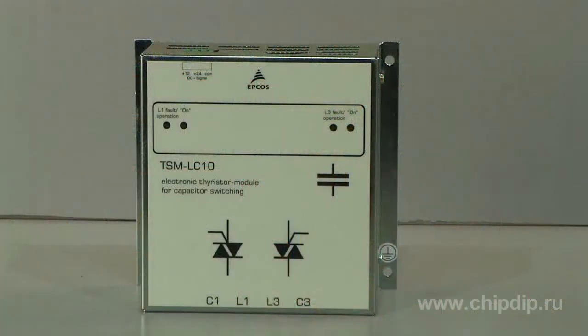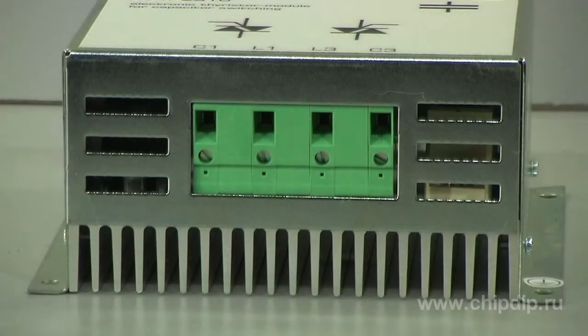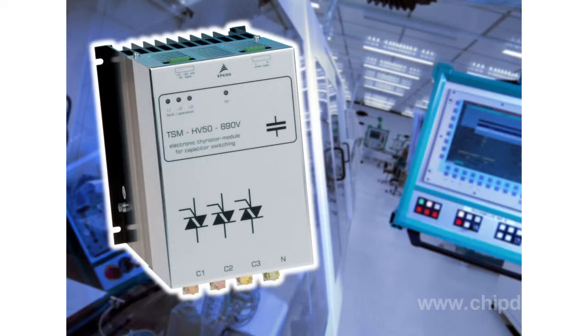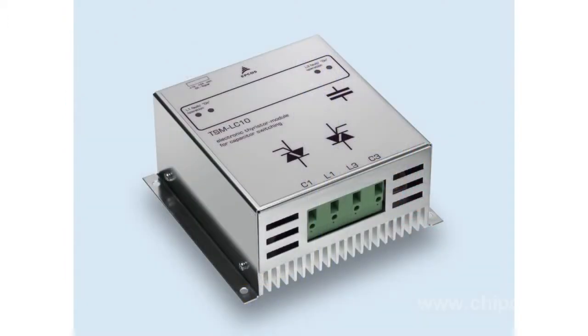The terminal block in these devices is not prone to wear, which is a clear advantage compared to electromechanical contactors. Besides, the thyristor module facilitates soft commutation between the capacitors in unlimited amounts and with unlimited frequency. Another plus is low response time enabled by a high-speed regulator and connection at a given moment of time. All this helps to save the life of the compensation unit stages.